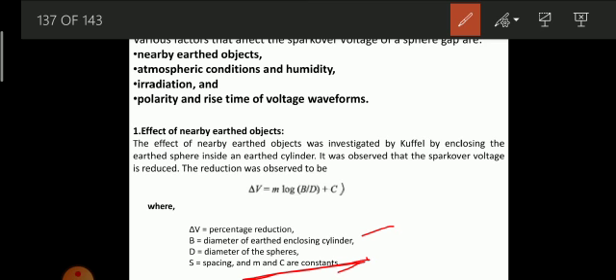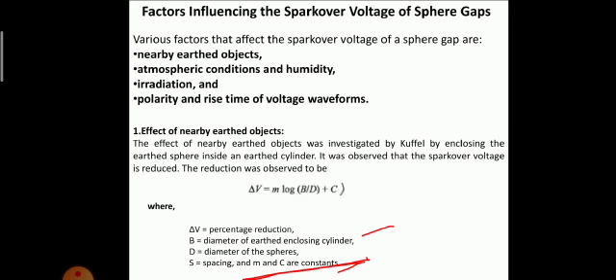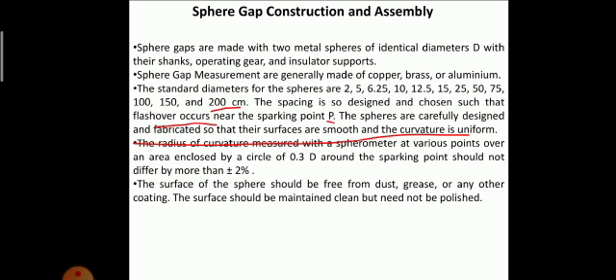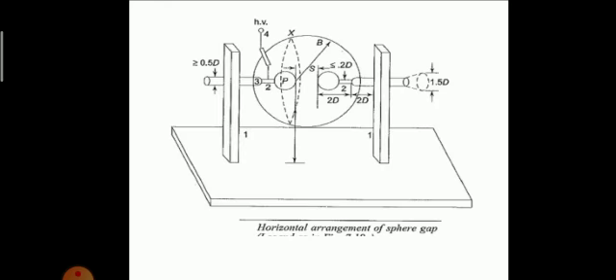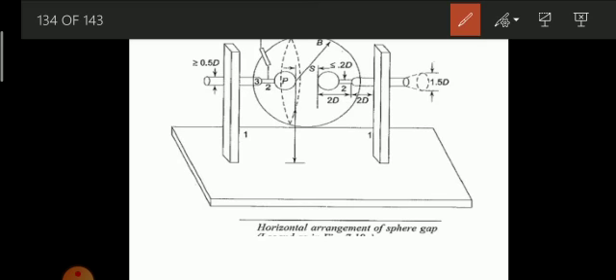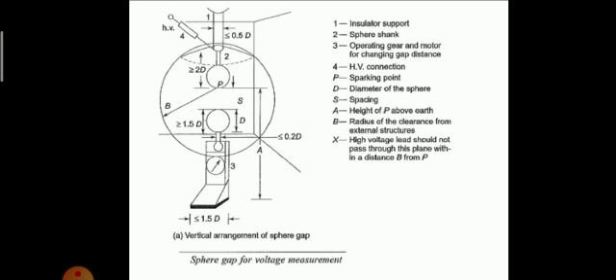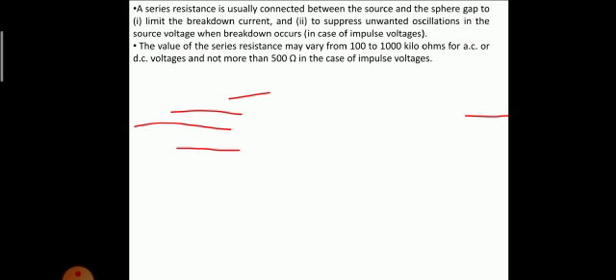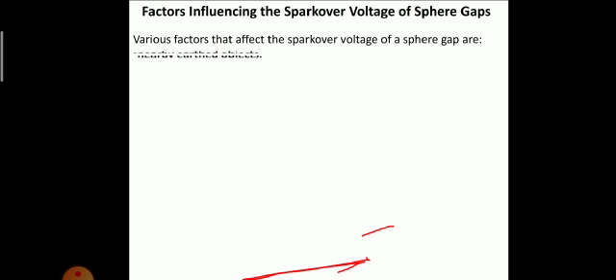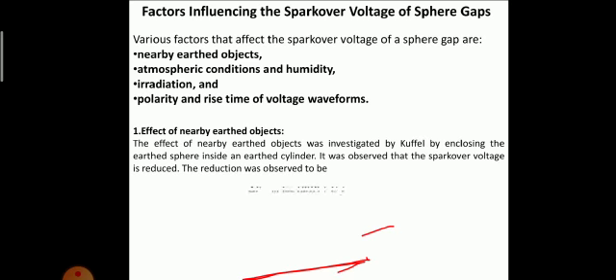Whatever reduction was measured by Kuffel was less than 2%, if the specifications regarding the clearances are closely observed. Here I have shown you the figure and given the clearances. You can see B in both the figures. B is the radius of clearance from external surfaces. Hence, if the specifications regarding the clearances are closely observed, the error is within the specified tolerances and accuracies. So the nearby earthed objects would not have a considerable effect on the spark over voltage.